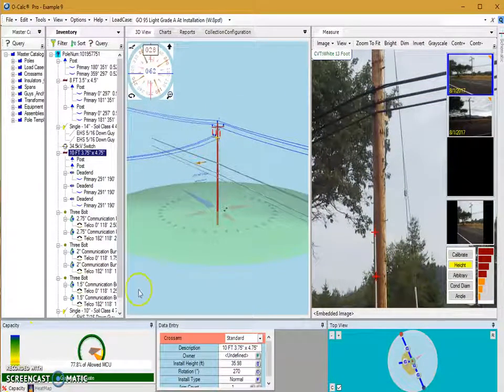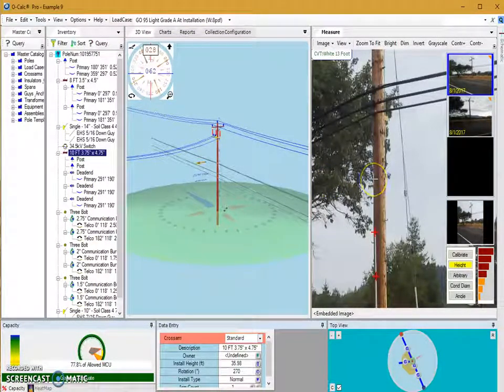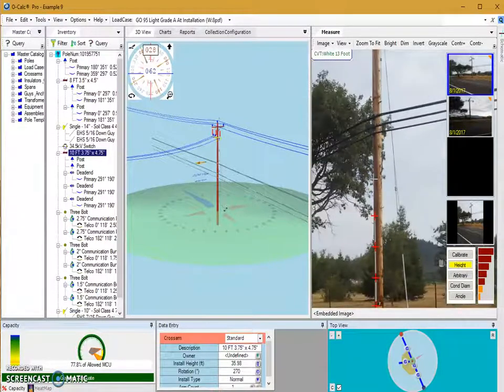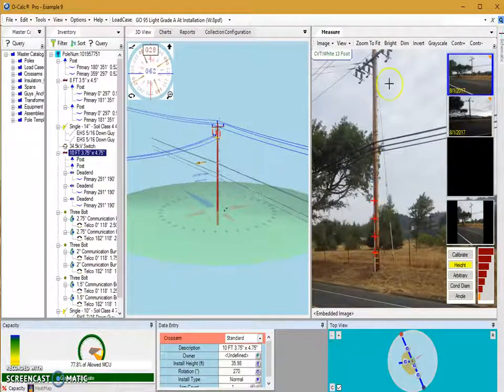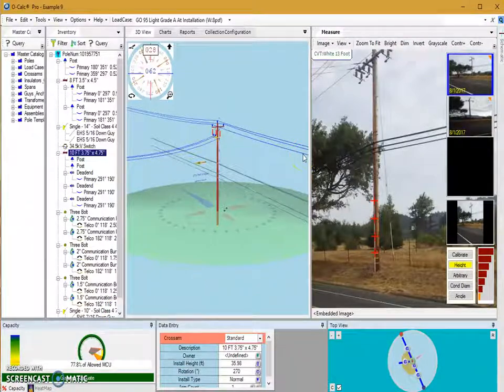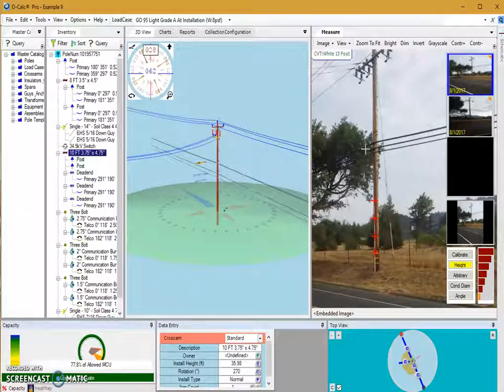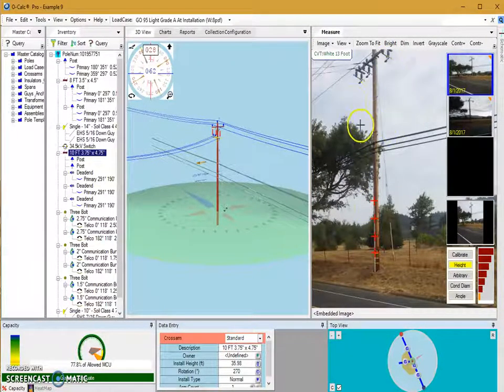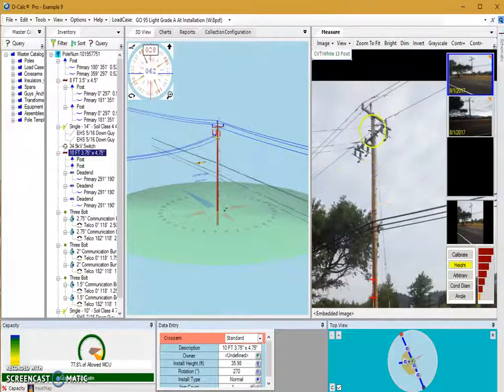Typically the first item adjusted is the setting depth of the pole. One of the things you can do after calibrating the photo is ensure that your setting depth being modeled is accurate, to get the most accurate capacity utilization number possible. Even though according to the NESC there are different specifications for what the setting depth should be, that doesn't necessarily mean it's exact, so you can check that using this tool.